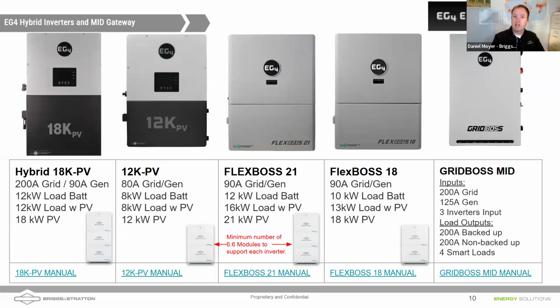These are really a game changer when it comes to having the flexibility of where to install a system, of having this centralized gateway or Grid Boss that allows all AC to come in and out. And I'll talk about the advantages as we get into it today. But I want to just talk about that 18K PV on the left, that has 200 amp pass-through. The ability to take in all 200 amps from a grid, from a home load, and pass it out onto the home load. 12K PV, that's 80 amps in and out.